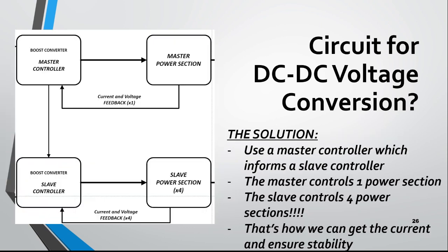The proper way to do this is with a master controller and a master power section, then copying that to a slave controller, and having that slave controller repeated a bunch of times until you have your desired output current. Each of these slave controllers and the master controller will have its own feedback and be able to control its output pretty accurately.